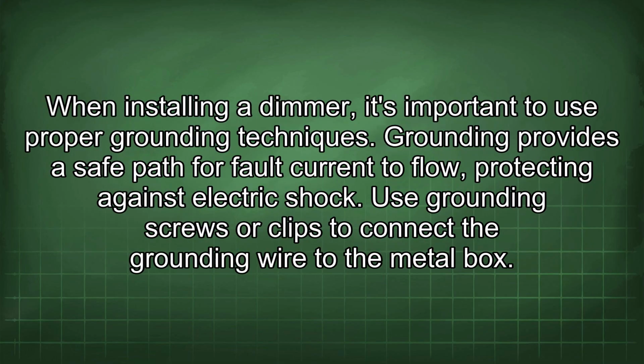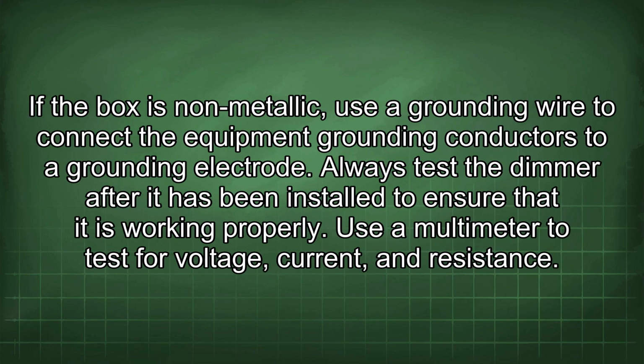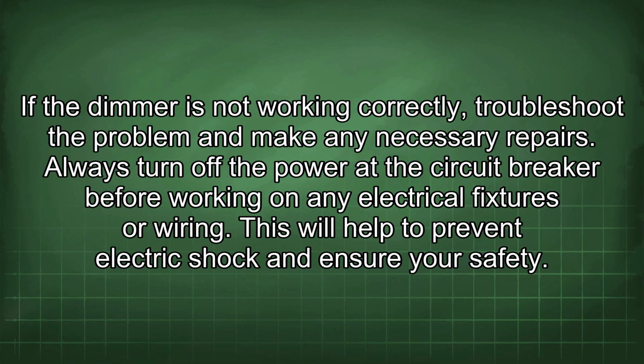When installing a dimmer, it's important to use proper grounding techniques. Grounding provides a safe path for fault current to flow, protecting against electric shock. Use grounding screws or clips to connect the grounding wire to the metal box. If the box is non-metallic, use a grounding wire to connect the equipment grounding conductors to a grounding electrode. Always test the dimmer after it has been installed to ensure that it is working properly. Use a multimeter to test for voltage, current, and resistance. If the dimmer is not working correctly, troubleshoot the problem and make any necessary repairs.